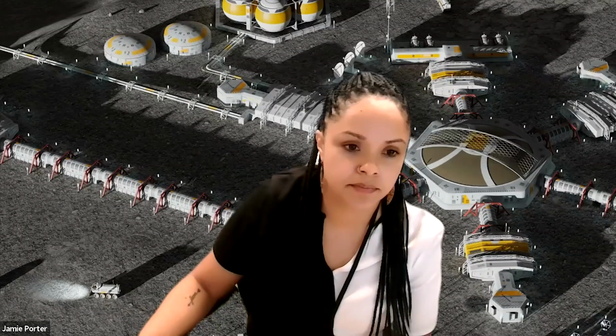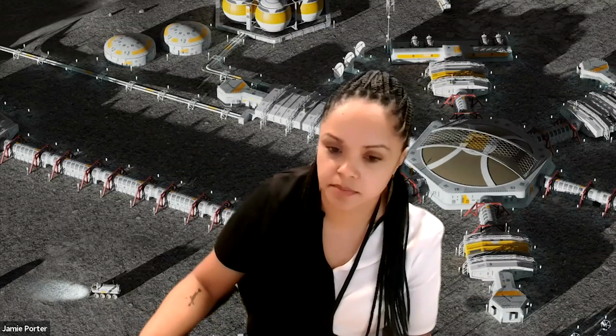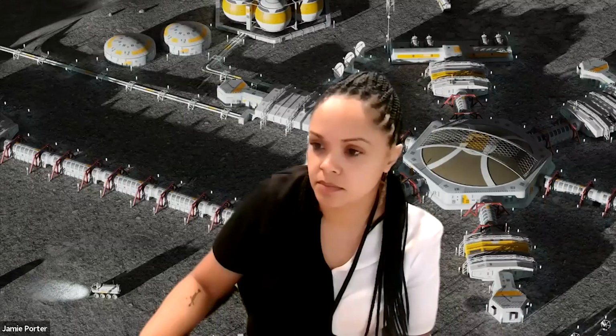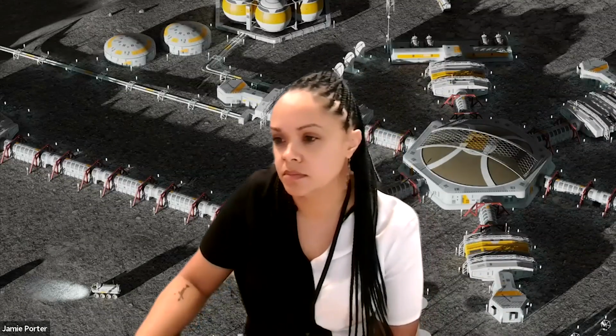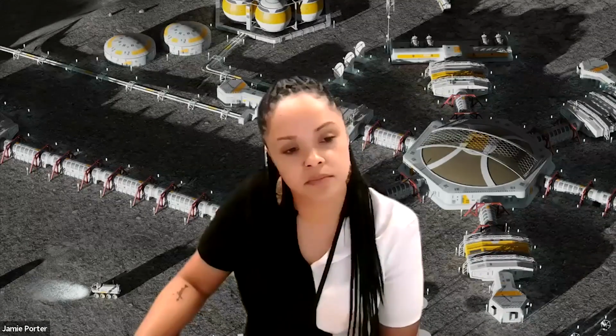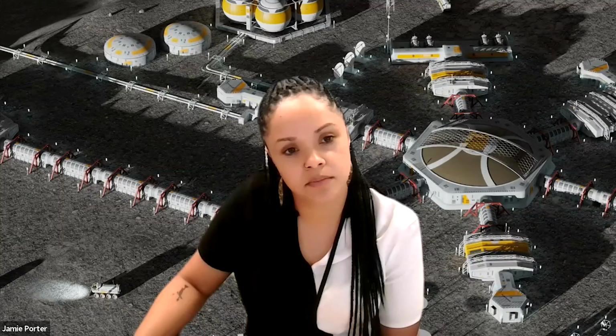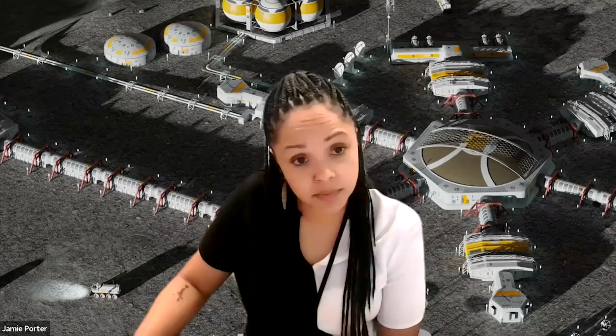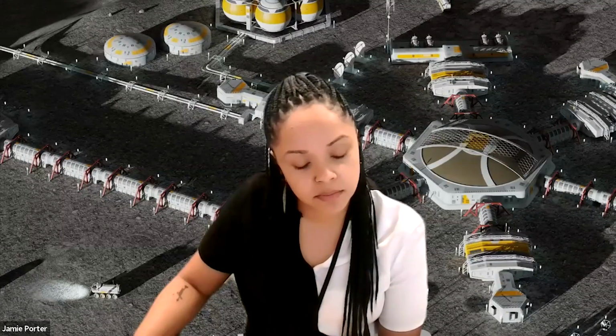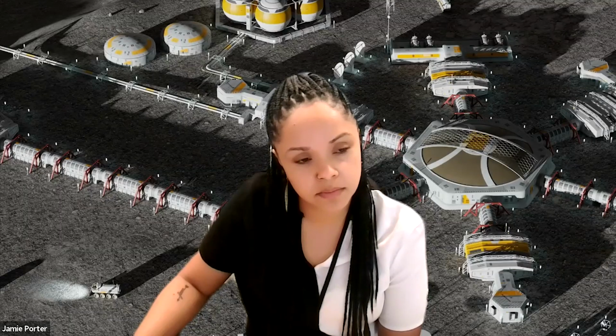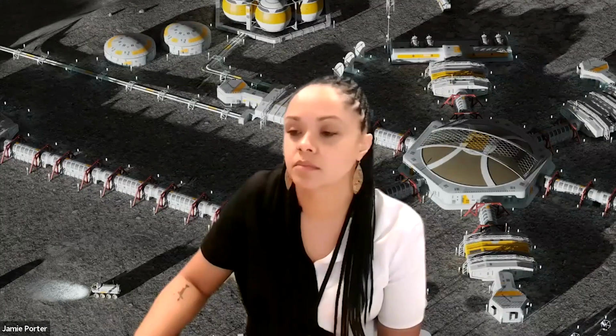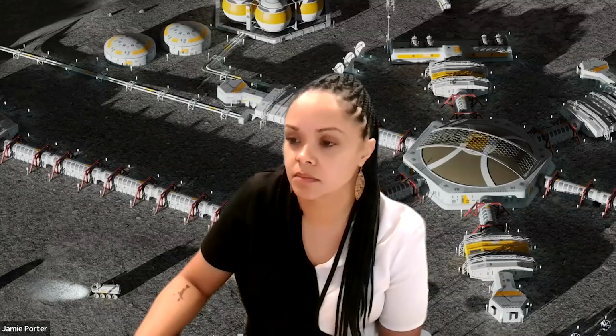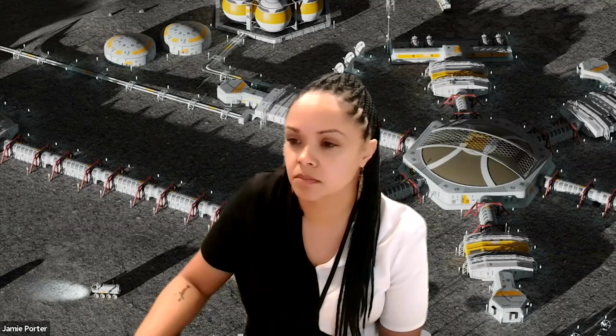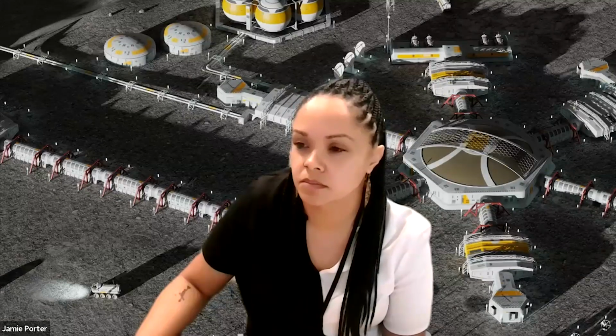All the current limiting RPCs on station have this hybrid circuit that has an issue. The issue has never been the tripping function in terms of it being a safety switch—it current limits and trips, that has never been an issue. The issue is that it trips autonomously for no reason other than a defect on the current level detector. That's where the reliability issue comes in, because you could potentially lose that load if you can't recover it.